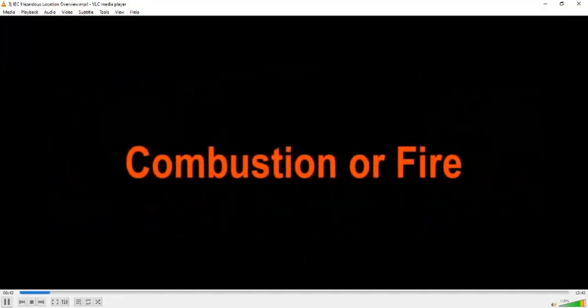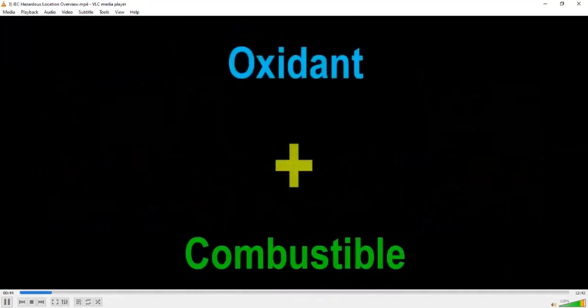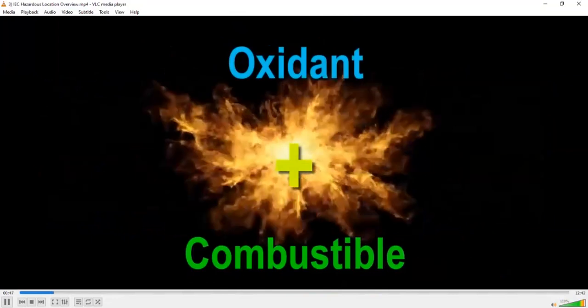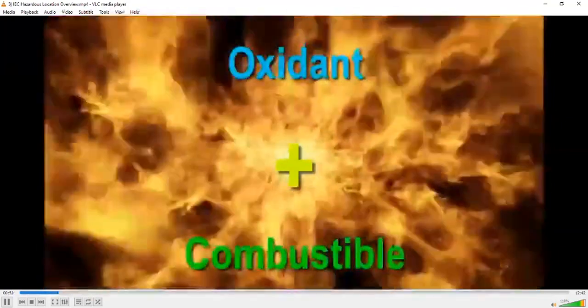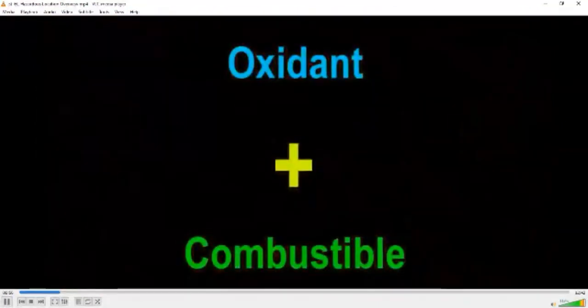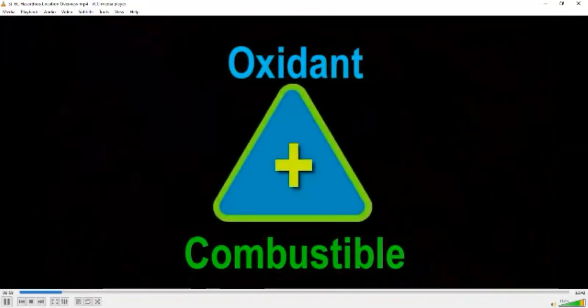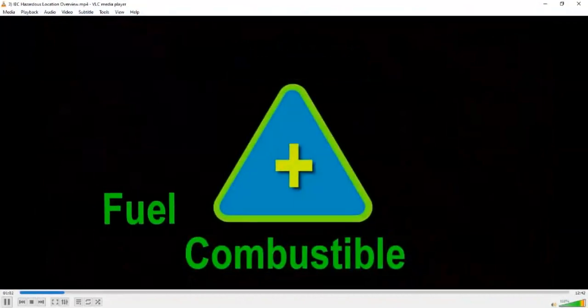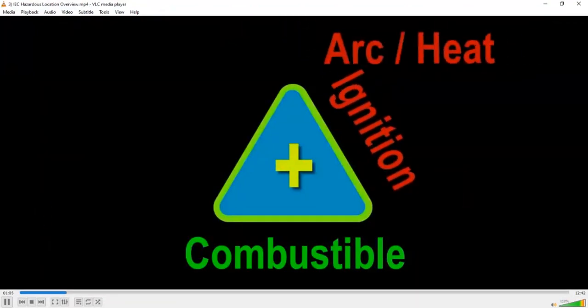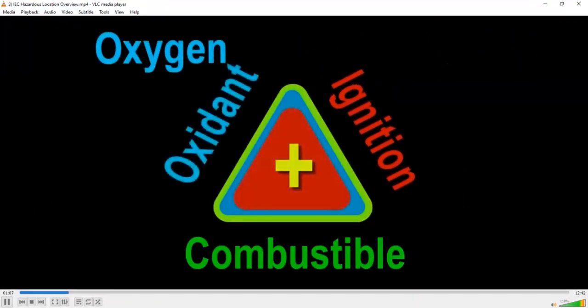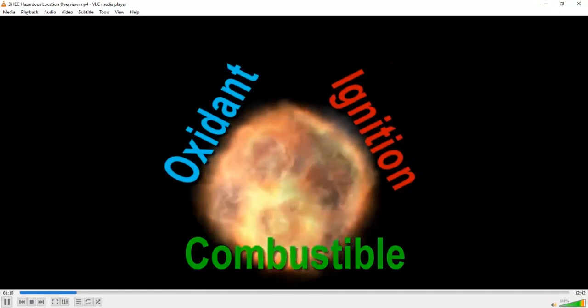Combustion or fire is a chemical reaction in which a combustible material combines with an oxidant to release energy. Part of the energy release is used to sustain the explosion by utilizing existing heat or creating a vacuum to consume more oxygen. Within a hazardous environment, there are three elements necessary for a fire or explosion: a combustible material, also known as a fuel, an ignition source, either electrical arcing or general heat, and an oxidizer, also known as oxygen. When a fuel, oxidizer, and ignition source are present at the necessary levels, burning or explosion will occur. To reduce the possibility of fire or explosion, one of the key elements needs to be reduced or removed.